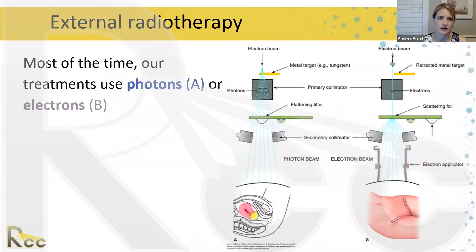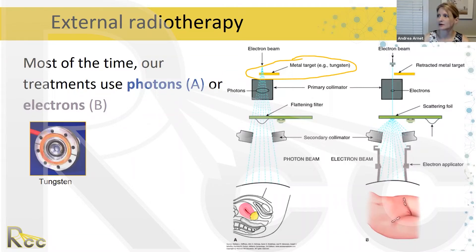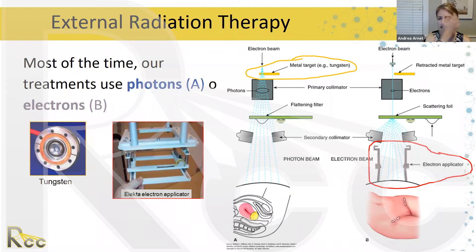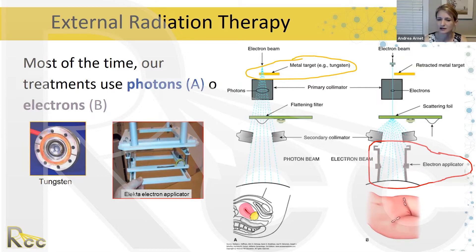Most of the time with external radiation therapy we use photons or electrons. With photons, an electron beam targets and passes through a metal target, then through a primary collimator, flattening filter, and secondary collimator before reaching the patient. For electrons, the metal target is retracted and the beam travels through a primary collimator into a scattering foil, then through a secondary collimator and electron applicator — used for shallow treatments such as skin cancers.